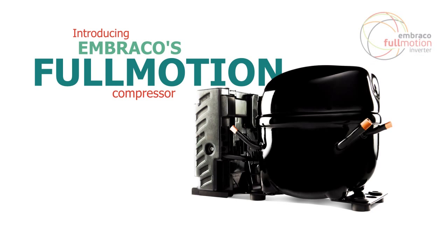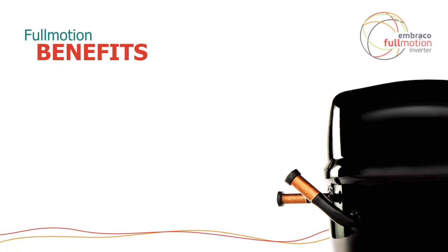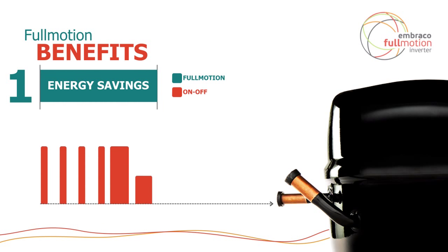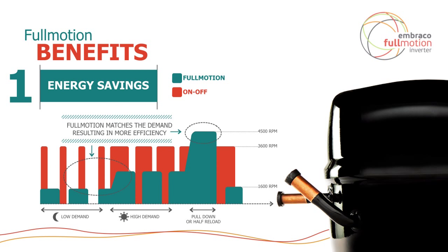One way is to use a full-motion variable speed compressor that uses R290 on the high side, and we worked with Thermo Fisher to apply it with R170 on the low side. This is a highly efficient compressor and it has what we call an overdrive feature, offering high reliability and low noise. The energy savings through load matching amount to around 20% to 40% improvement in EER depending on the application. Under low demand situations, the compressor operates at a lower speed — say 2,000 RPM — keeping run times longer in a more energy-efficient state than a fixed-speed compressor cycling on and off.